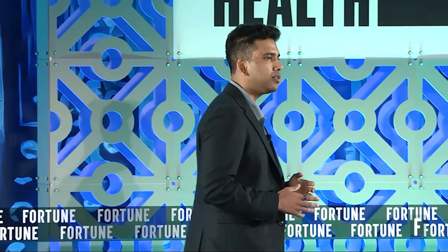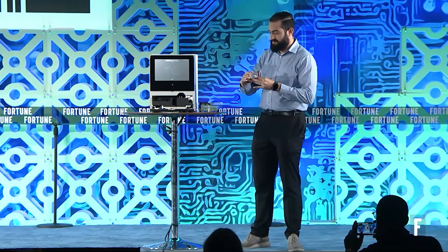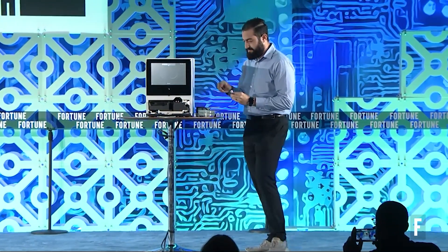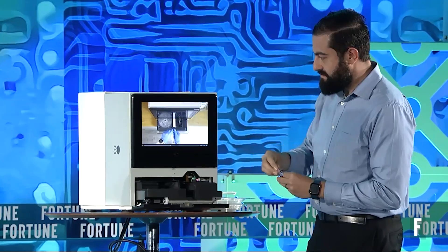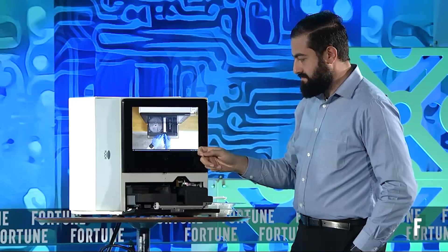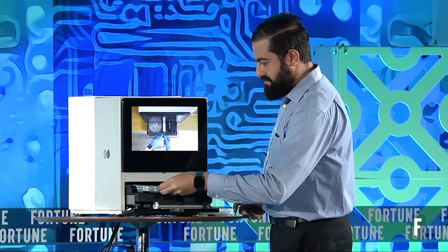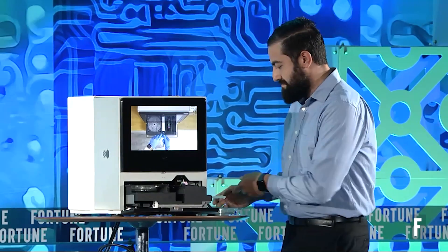The Vital One only uses 600 microliters of blood — that's less than 3% of what's typically used for a comprehensive panel like this. What that means is you can use either vacutainers or microtainers from a finger stick sample. Munir's going to drop the microtainers today into the Vital One, and then he's going to slide in our two consumable components: a disk pack and a support pack.